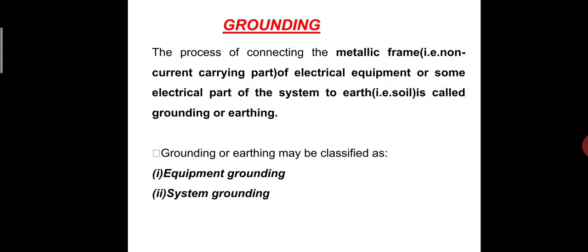The neutral grounding is important in power system practice because: first, earth fault protection is based on the method of neutral earthing; second, the system voltage during earth fault depends on neutral earthing; third, neutral earthing has associated switchgear; fourth, neutral earthing is provided basically for the purpose of protection against arcing grounds, unbalanced voltage with respect to earth, protection from lightning, and for improvement of the system.